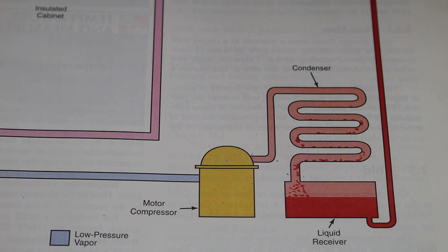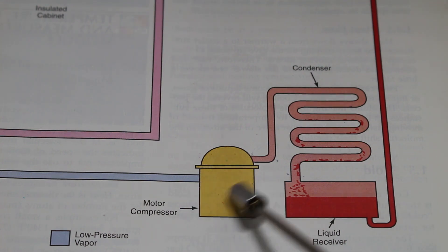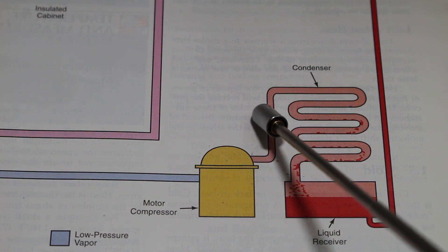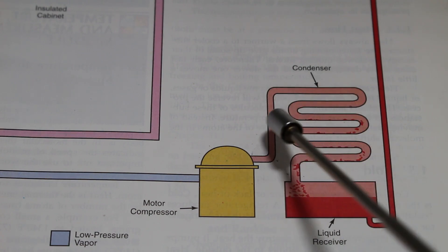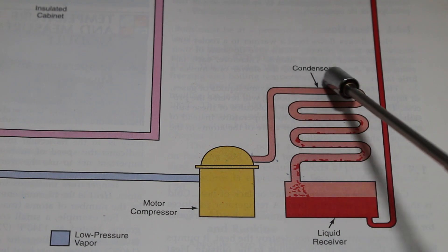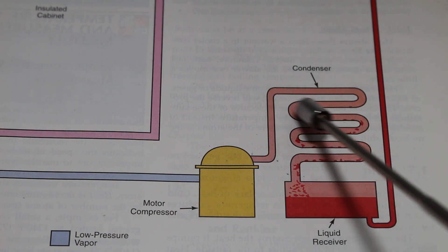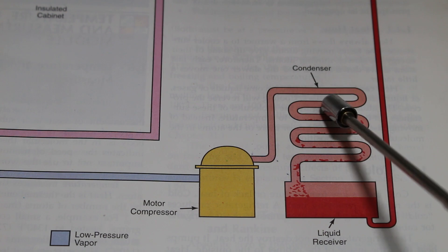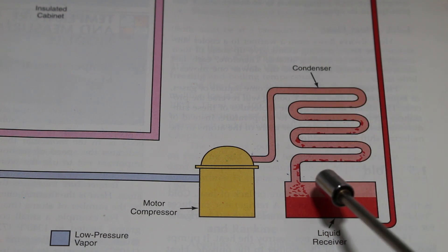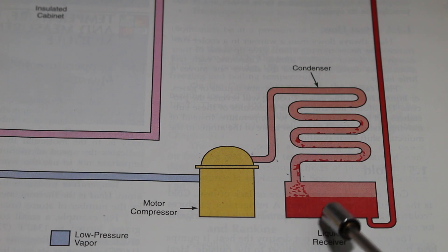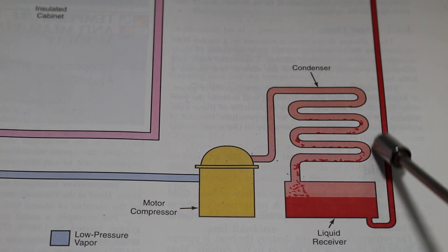This change in state can be calculated in BTUs, but that will be postponed for another lesson on what is a BTU. Leaving the compressor is the discharge line, where we are a high temperature, high pressure, superheated vapor. And when we enter our condenser, we actually change state from a high pressure, high temperature, superheated vapor into a high pressure, high temperature, subcooled liquid.